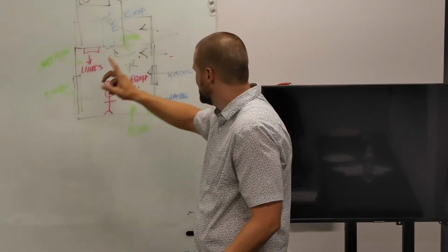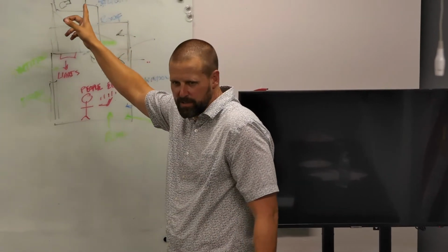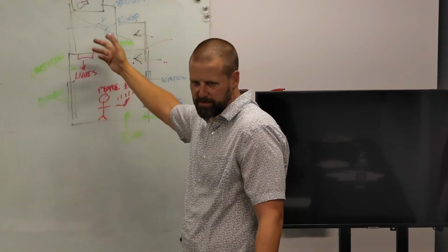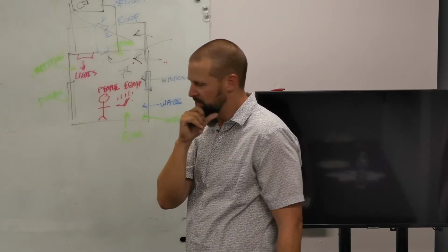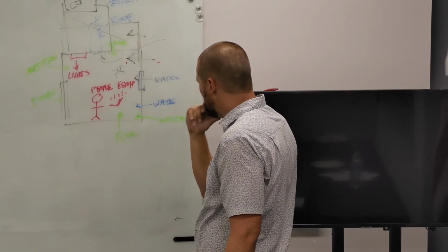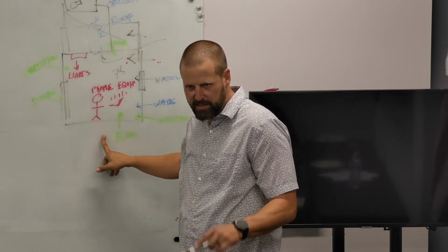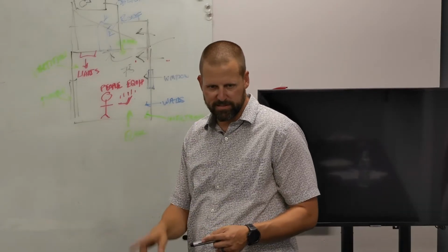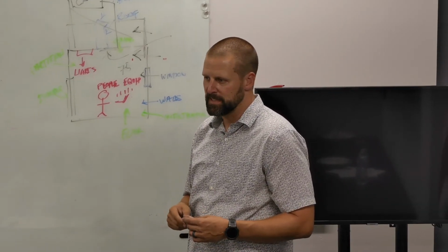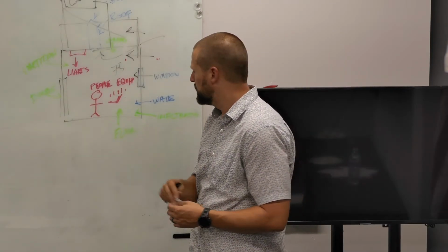Okay, so we got ceilings, we got partitions. Skylights are kind of like windows, but they're on the roof. Roofs are kind of like walls, but they have more requirements, like we talked about. Floors we generally ignore, but the ground temp there is heat transfer there. It's pretty negligible in Southern California. It might be a bigger deal elsewhere.